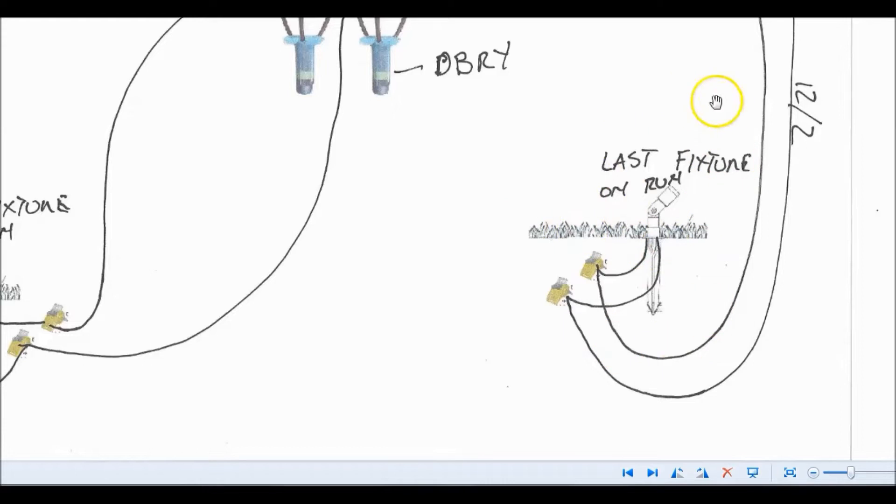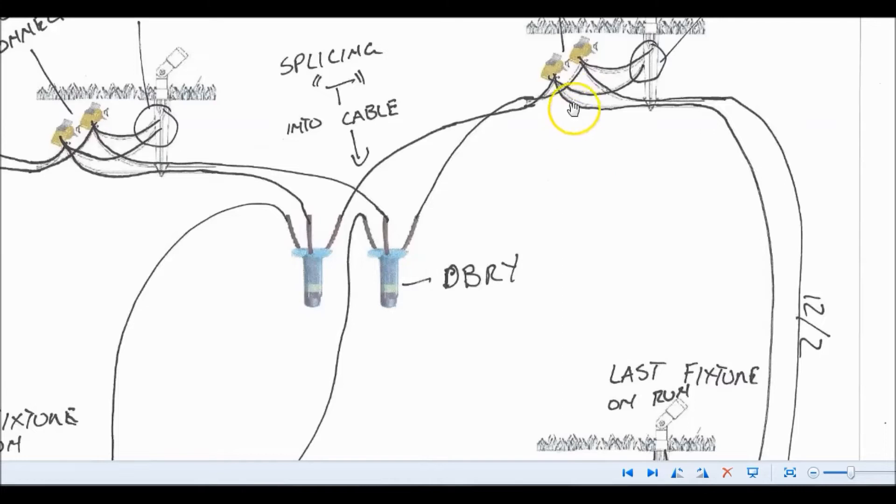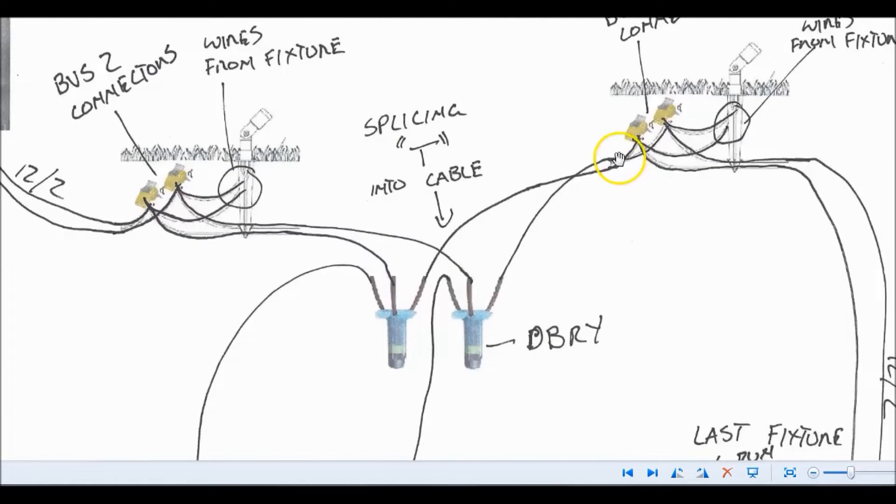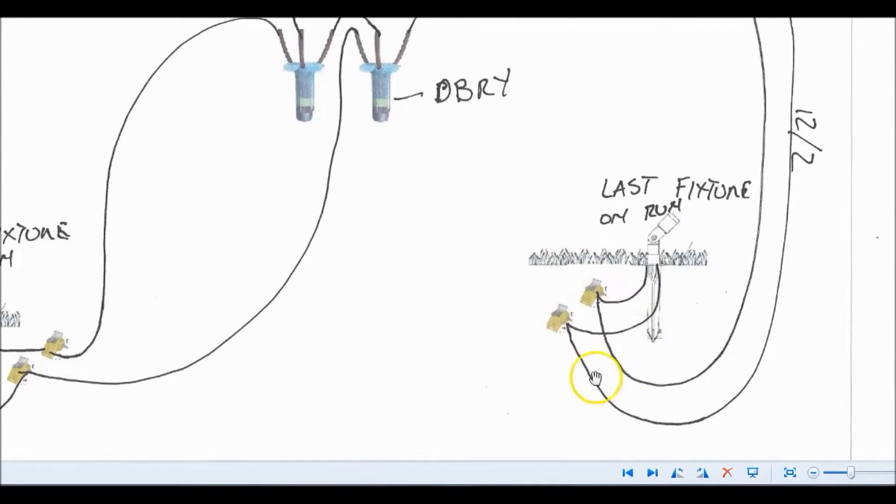Another question I get asked all the time: what about the last fixture? Well, you still have the same three ports on the connector, but on your last fixture the 12-2 wire still comes in. One of those two wires goes into the BUS-2 connector, and the fixture wire still goes into the smaller port. You do that with both wires from the 12-2. So in essence, the last fixture on the run is only going to have two wires going into each connector — as opposed to in-line fixtures that have three: in, out, and fixture wire.